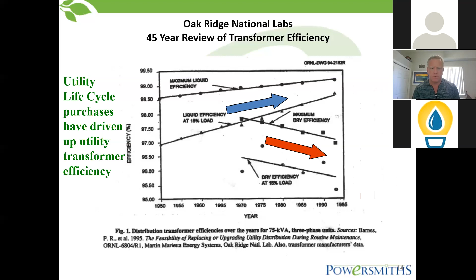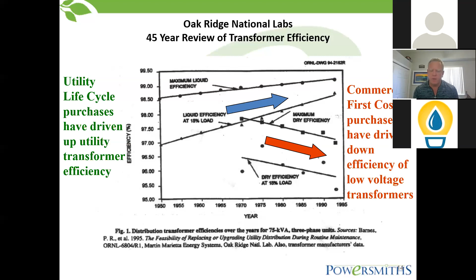Here's another study, done by Oak Ridge National Labs. Over the last 45 years, oil filled transformers, the green ones that sit outside, owned by the utility, have gone up in efficiency and lower losses, because it was driven by the utility. If you think about it, the output of that transformer, any losses in it, comes out of the utility's back pocket. Conversely, dry type transformers over the last 45 years have gone down in efficiency and up in losses, because it's about first cost, the cheapest one you could buy. You go down to Graybar, say I need a 75 kVA transformer, give me the cheapest one, I'll put it in. That's essentially what you had up until about 8 years ago.